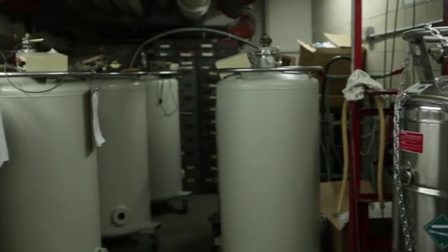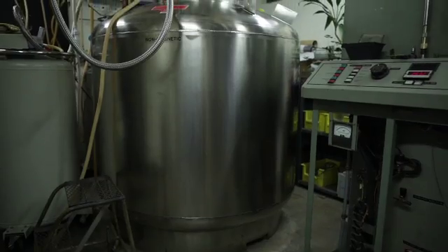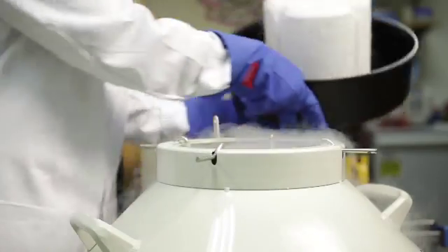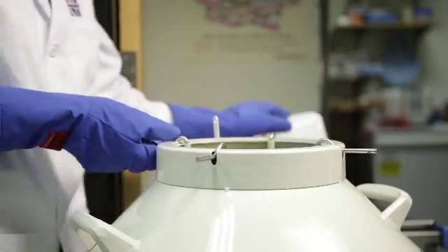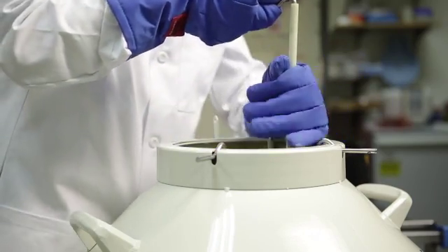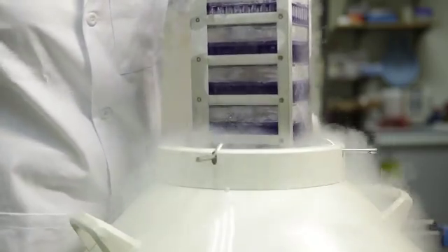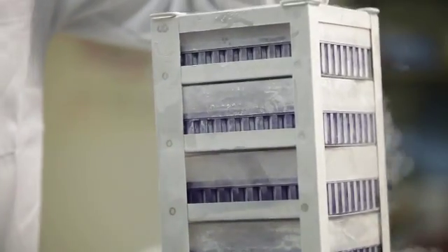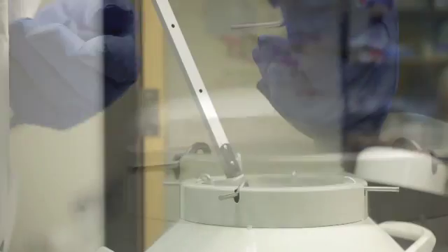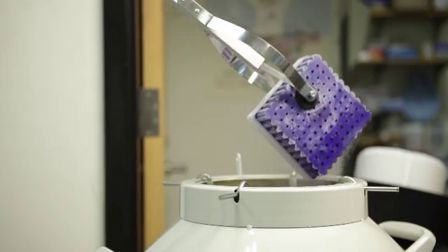Pressure relief settings and tank styles for other cryogens like carbon dioxide, argon, helium, oxygen, or hydrogen may vary. Cryotubes or vessels stored under liquid nitrogen may rupture without warning when removed from a liquid nitrogen dewar. One reason this occurs is that liquid nitrogen has seeped inside the cryovial or along the threads of the cap. Another reason is that liquid nitrogen-cooled vessels or traps condense and liquefy oxygen from the air. Never reach into liquid nitrogen — always use a mechanical device to retrieve items.